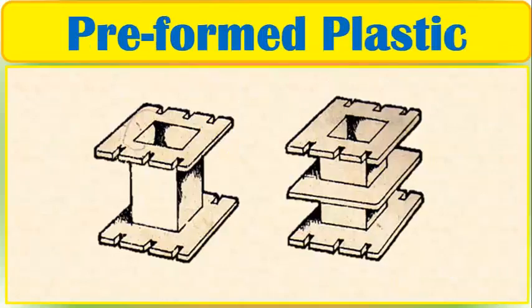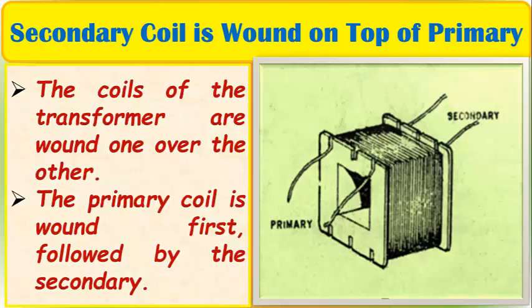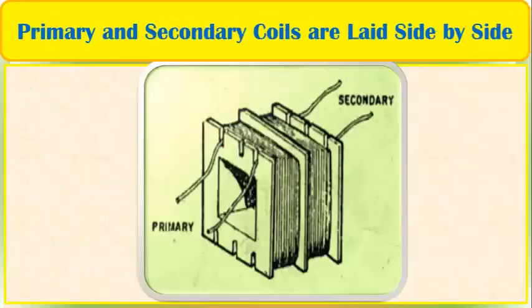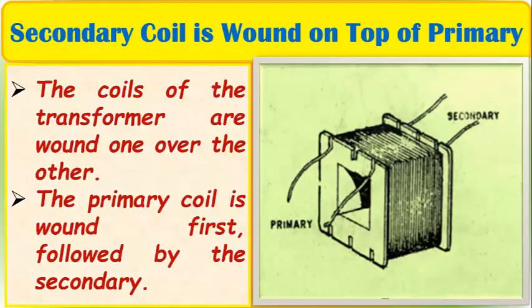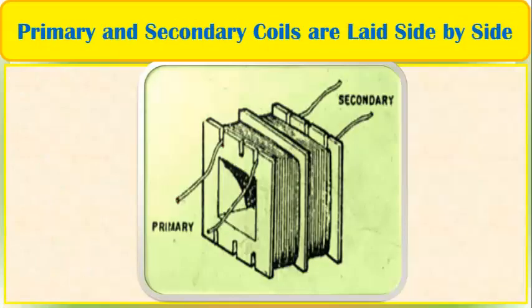This illustration is the preformed plastic. Secondary coil is wound on top of primary. The coils of the transformer are wound one over the other. The primary coil is wound first, followed by the secondary. So this is now the illustration of the primary and secondary coil, which are laid side by side. Small transformers usually do not use insulating material laid between layers of the coil. Wind continuously one layer over another until the coil is completed.